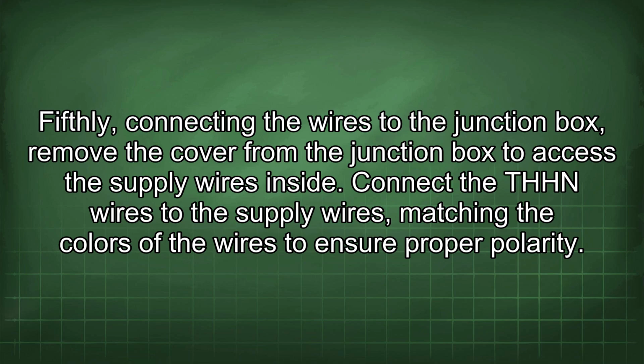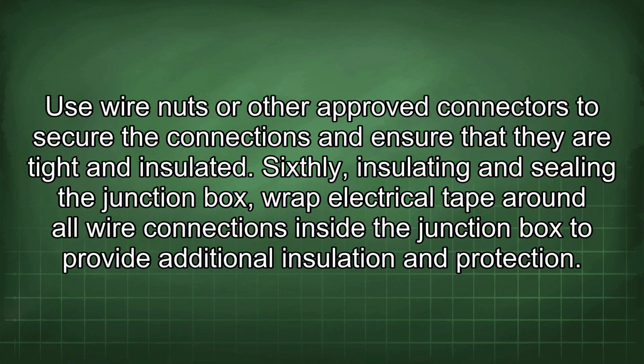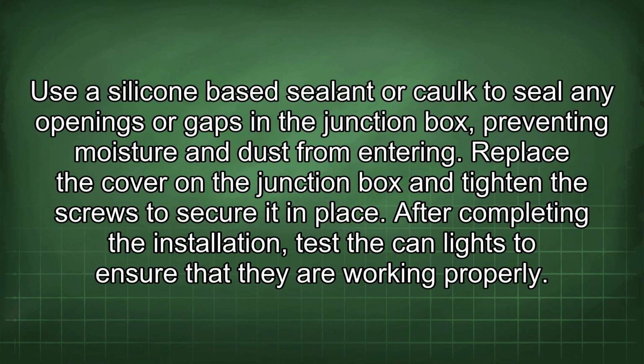Remove the cover from the junction box to access the supply wires inside. Connect the THHN wires to the supply wires, matching the colors of the wires to ensure proper polarity. Use wire nuts or other approved connectors to secure the connections and ensure that they are tight and insulated. Sixthly, insulating and sealing the junction box. Wrap electrical tape around all wire connections inside the junction box to provide additional insulation and protection. Use a silicone-based sealant or caulk to seal any openings or gaps in the junction box, preventing moisture and dust from entering. Replace the cover on the junction box and tighten the screws to secure it in place.